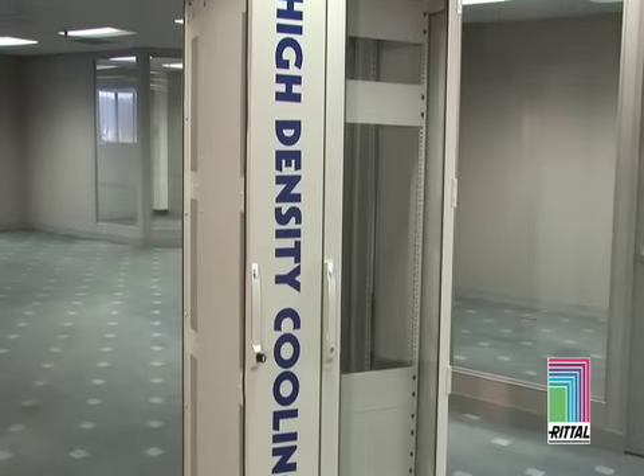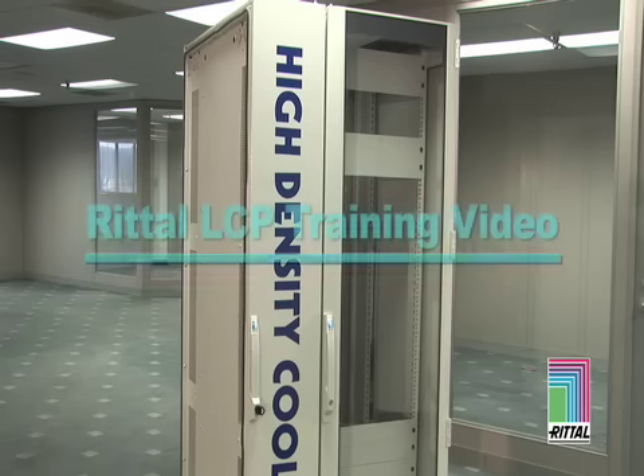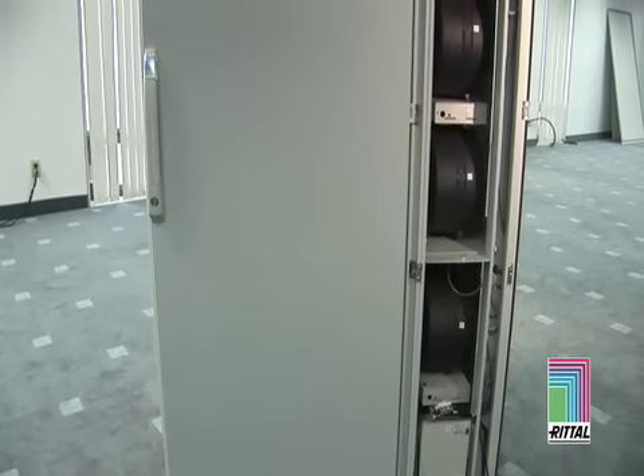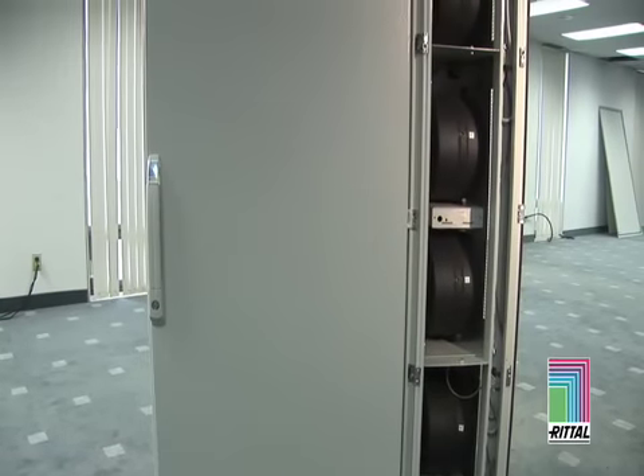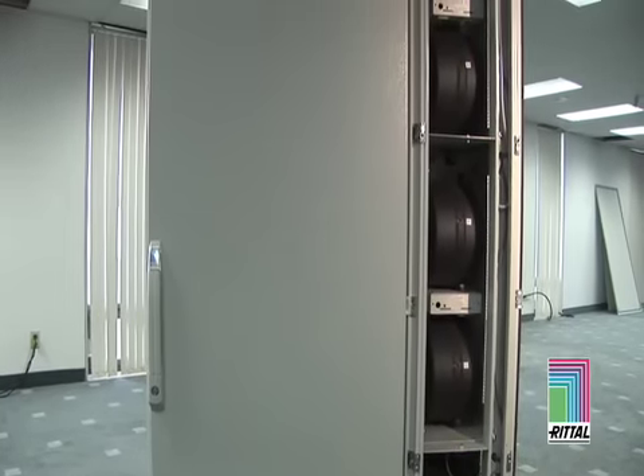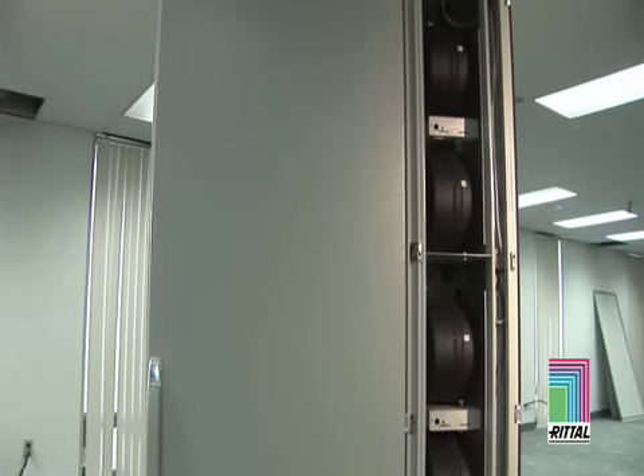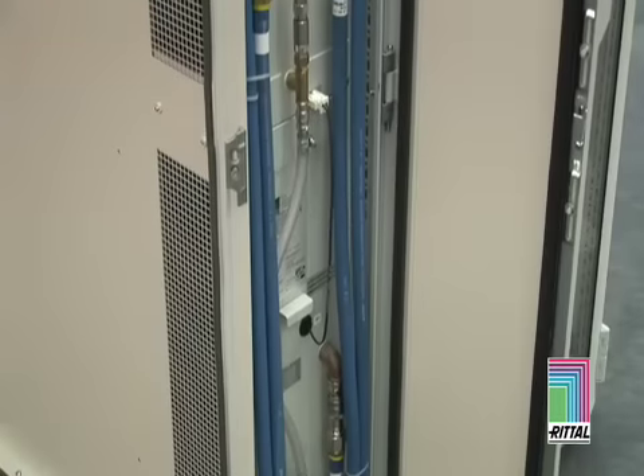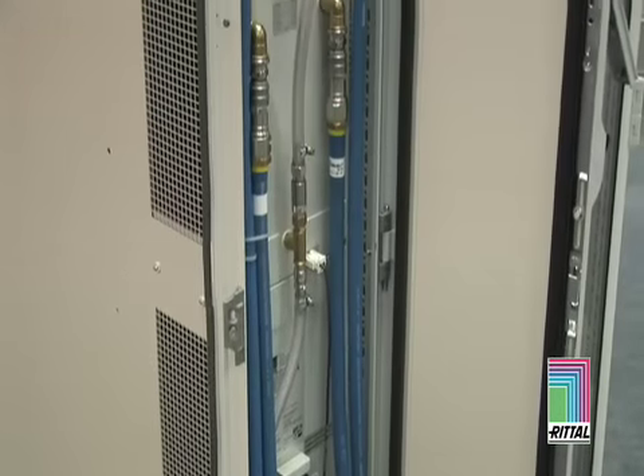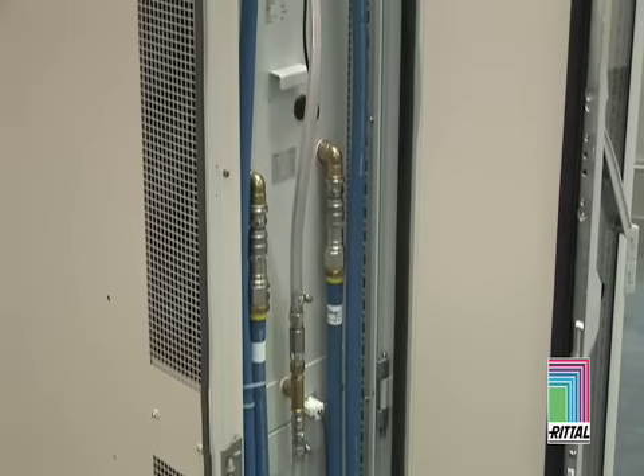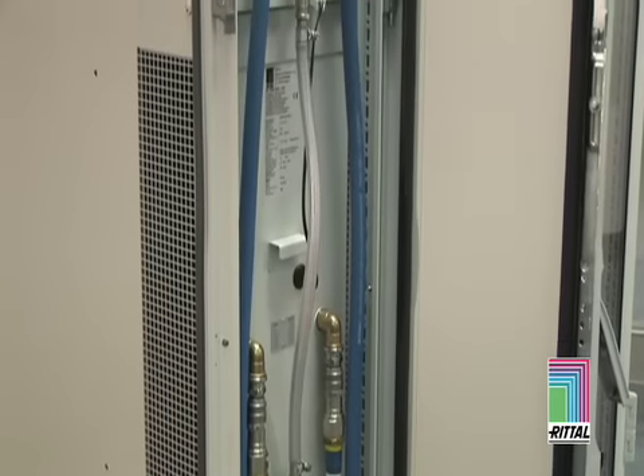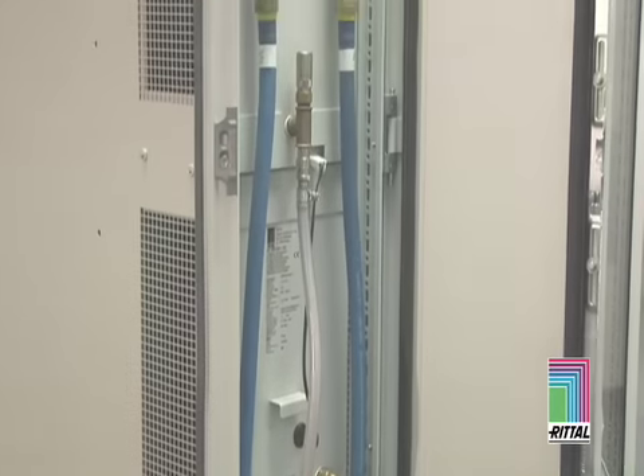Introduction to the Rittal Liquid Cooling Package, also known as the LCP. The LCP consists of 3 high-performance water-air heat exchangers, 3 fan module pairs, and an environmental control system to manage and report the operation of the unit. These parts give the LCP the ability to cool up to 20 kilowatts of installed IT load while maintaining precise control of the cold air temperature being delivered to the servers.